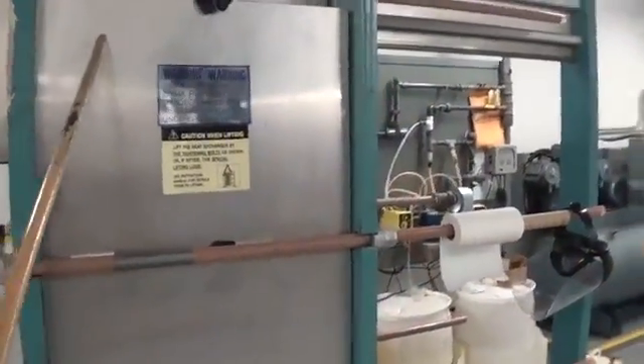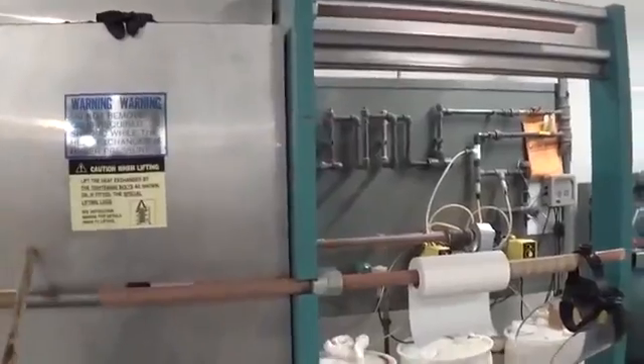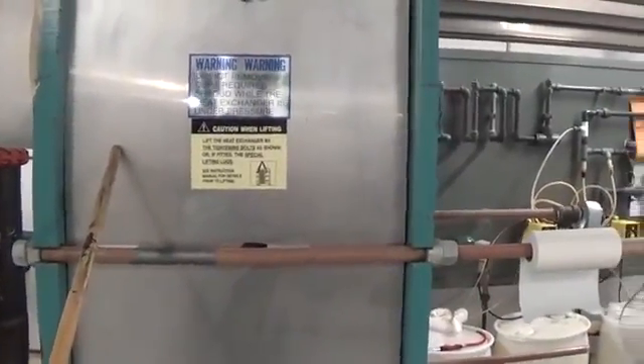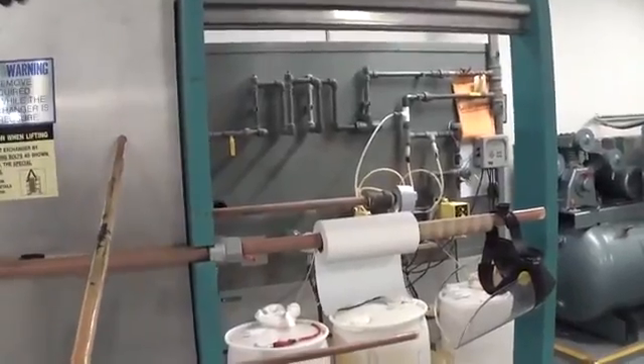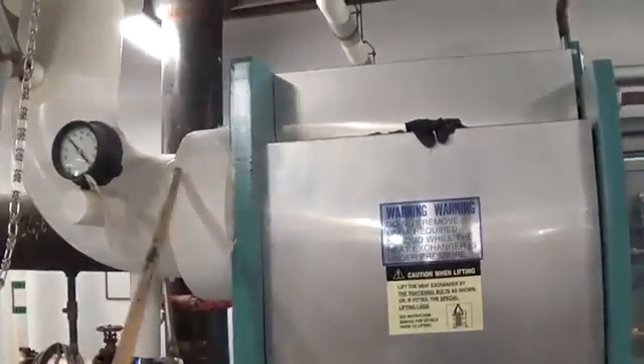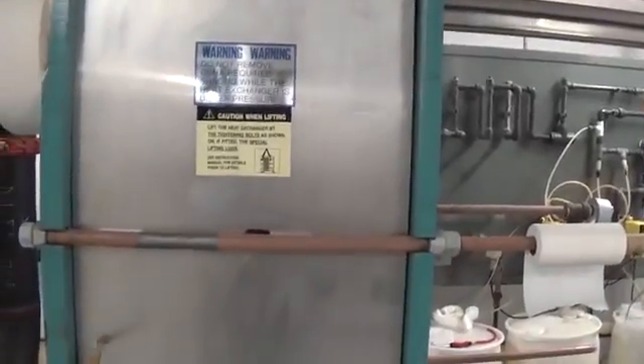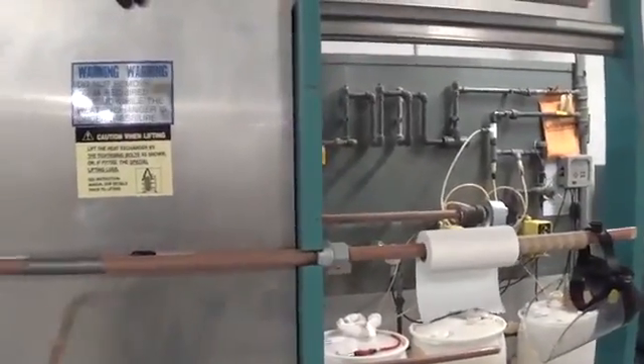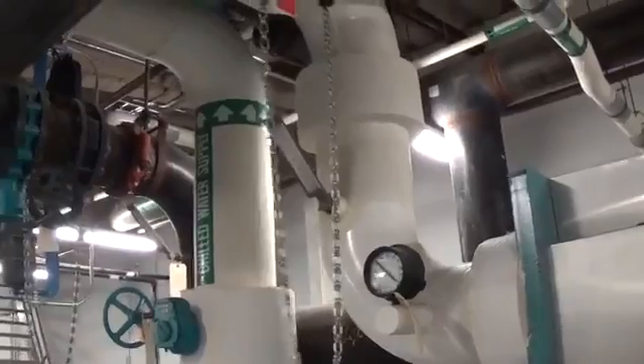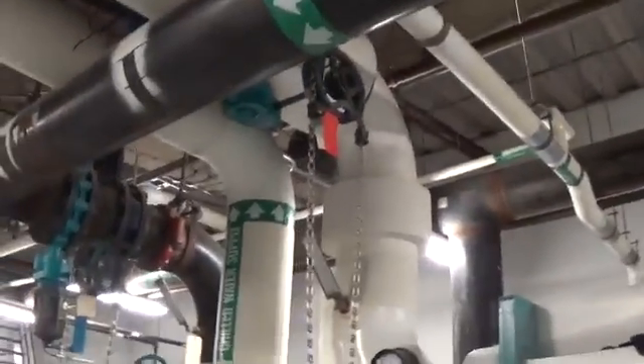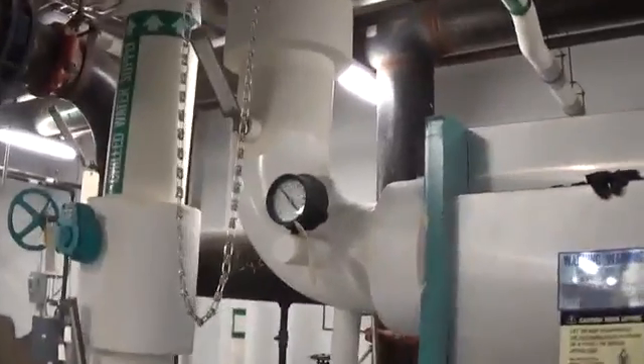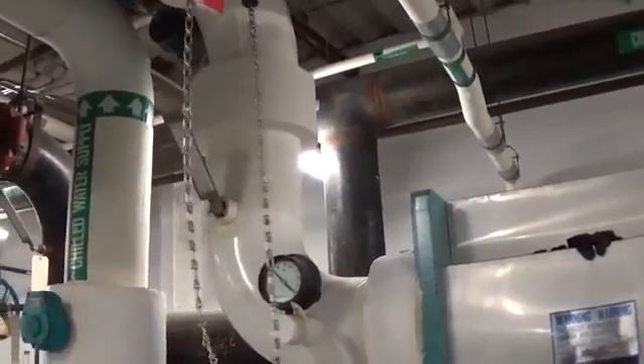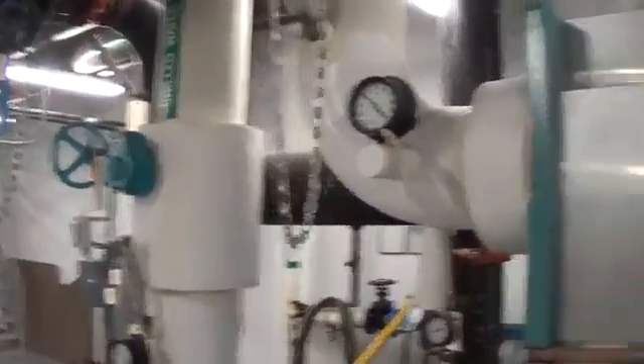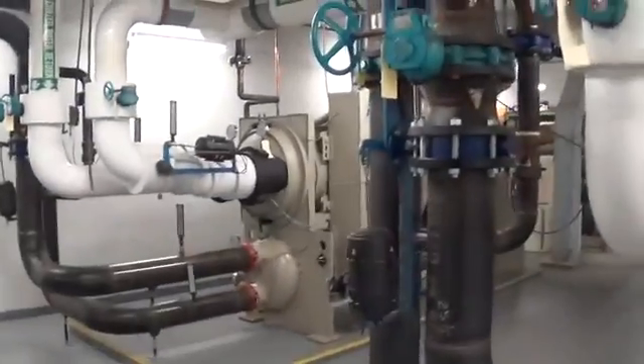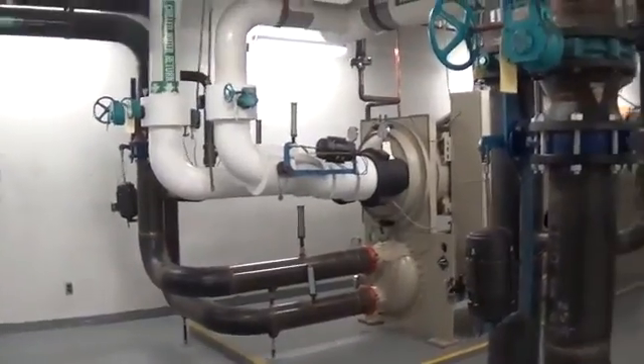it through this machine, which is basically just a bunch of copper plates, and migrates the cold water from the outside to the warm building chilled water, which comes in there, and therefore through principles of physics, it takes the cold water and makes free chilled water, courtesy of nature. So that's a pretty cool operation. There's a series of valves up there. If this water gets too warm, it'll shut these valves off automatically, and then once more just turn your chiller back on to have the mechanical cooling. So pretty cool little system.